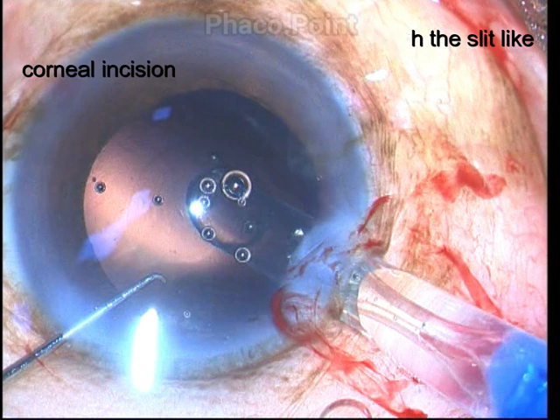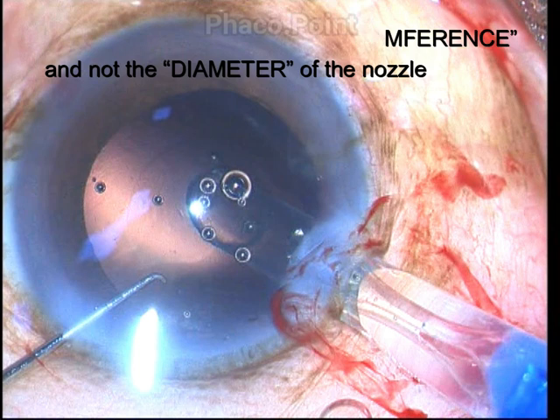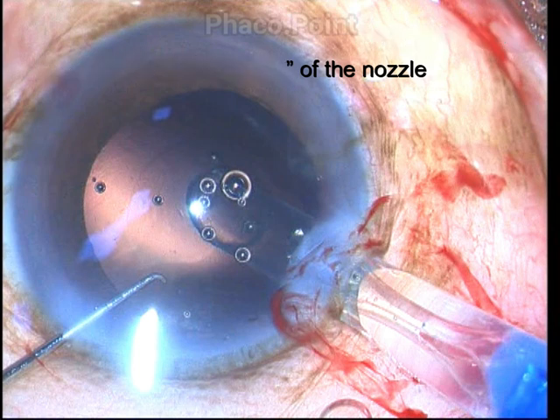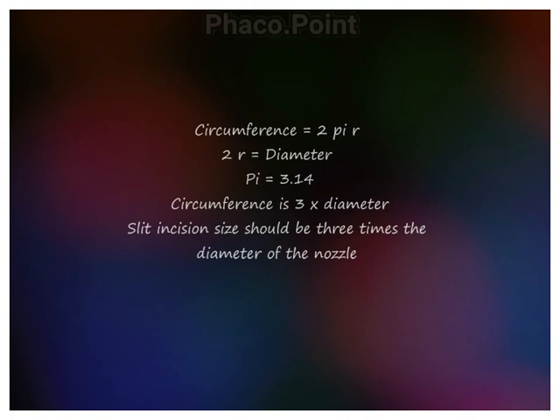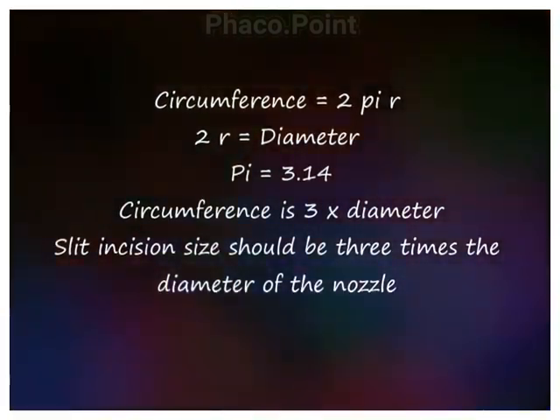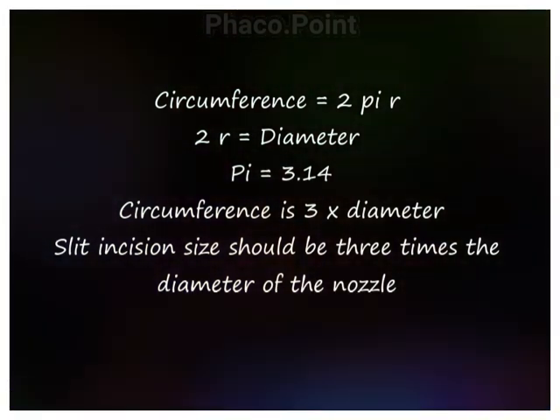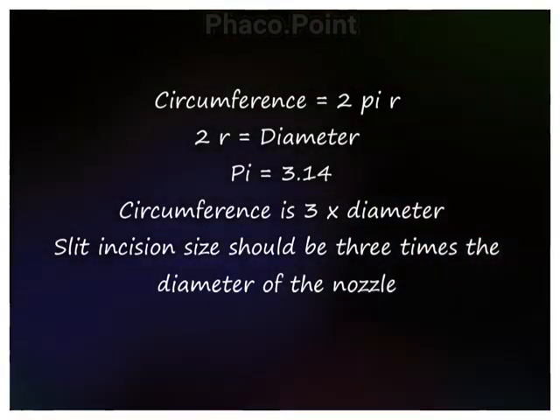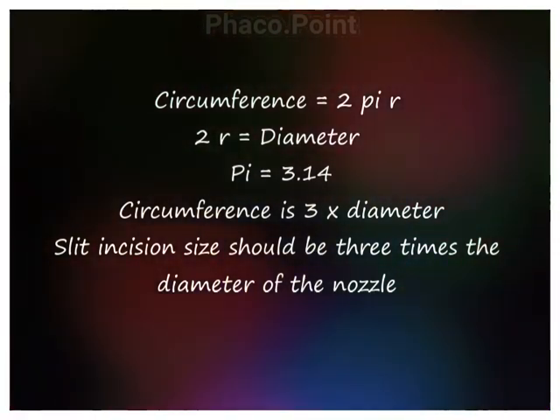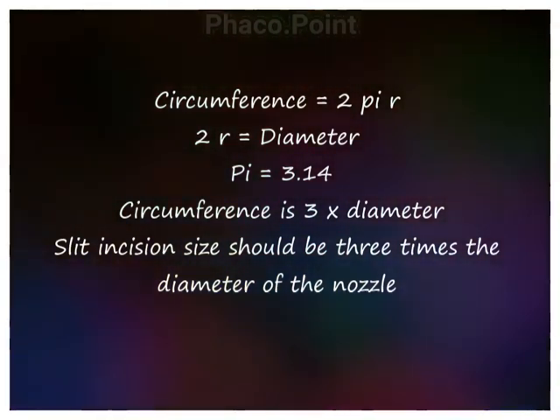For smooth, effortless and resistance-free insertion of the nozzle, its circumference and not its diameter should match the size of the clear corneal incision — this is an important concept to understand. We know that the circumference of a circle is given by the formula 2πr, where r is the radius and π has a numeric value of 3.14. Since twice the radius equals the diameter, it follows that the circumference of a circle is approximately three times its diameter.